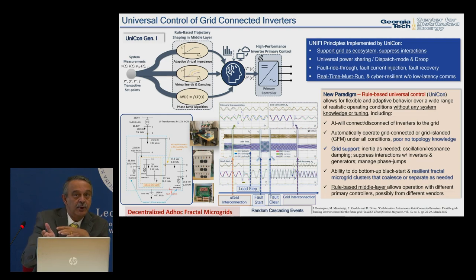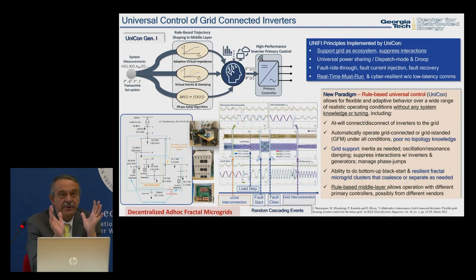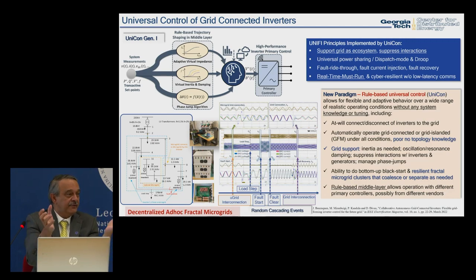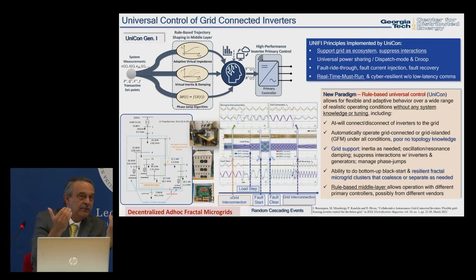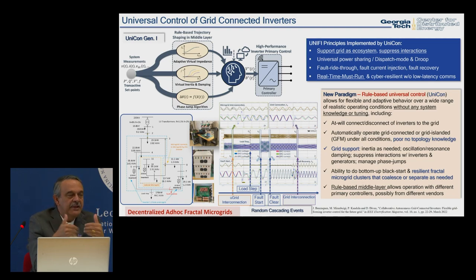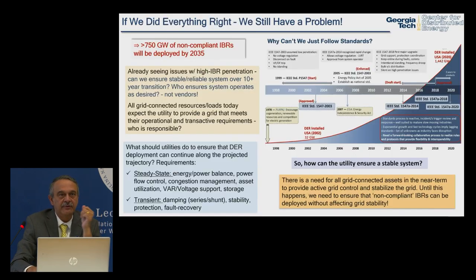Universal control means: connect and disconnect inverters at will, automatically operate in either grid-connected or islanded mode with no topology knowledge, provide grid support including damping and inertia, suppress interactions, form microgrid clusters automatically, and do it so that multiple vendors can implement this. We've demonstrated a decentralized ad-hoc fractal microgrid concept that can handle any disturbance in a small system.